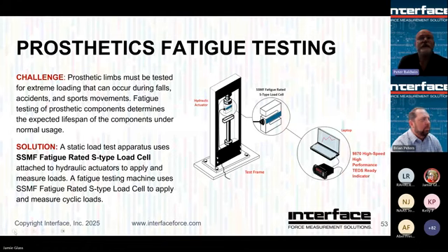For prosthetics, right? If any of you have done any work with FDA, I can, by my own experience, any sort of pacemaker type operation, everything has to be tested quite thoroughly. Well, so do prosthetics. And so for the fatigue testing, they use one of our S load cells, in this case, a fatigue rated load cell, into our 9870, which then was put through a PLC into a laptop so that you could monitor the data.